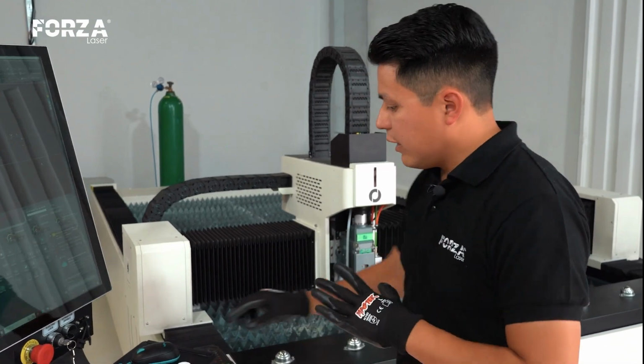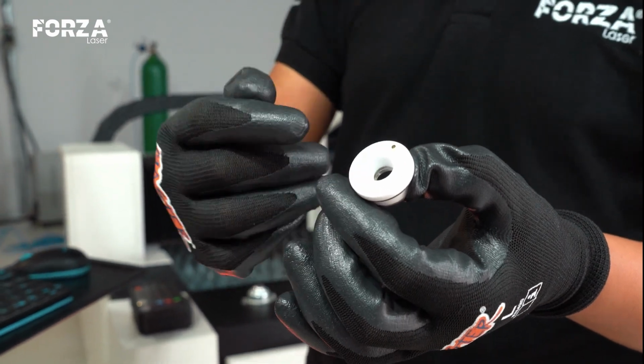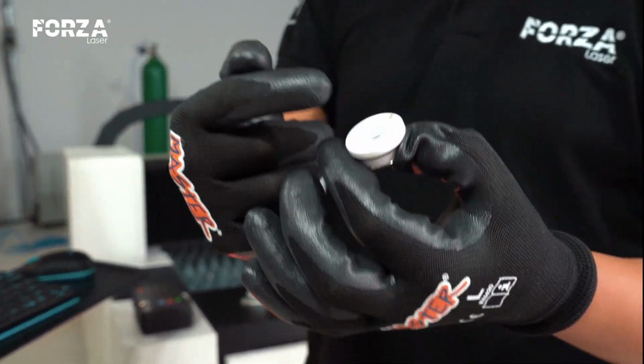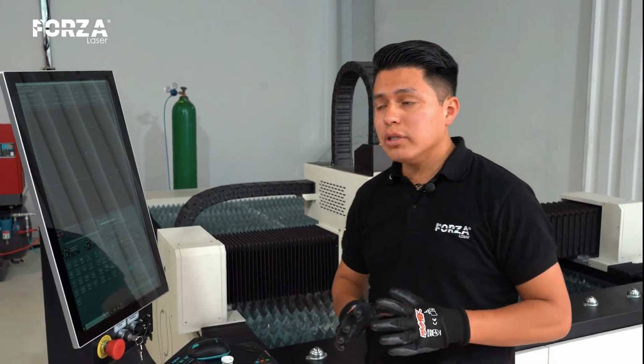This happens because that ceramic sensor has a little pin inside that's meant to stay in contact with the internal base. Now, if that pin gets loose or disconnected, the system immediately triggers this alarm and shows it on the screen. How to fix it?